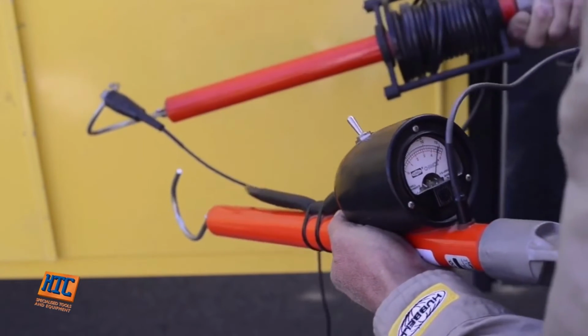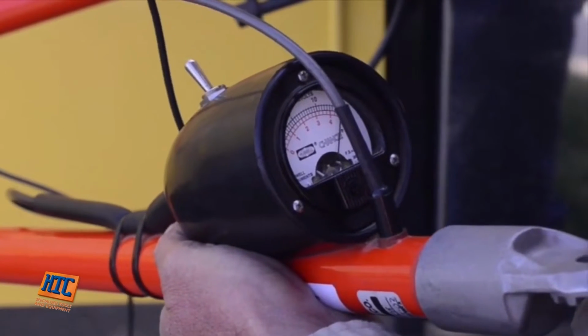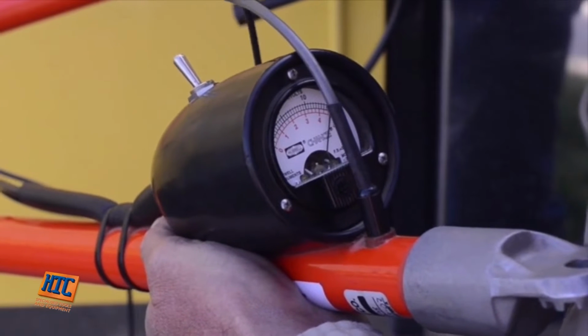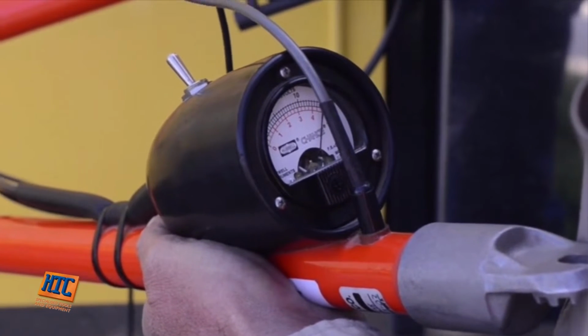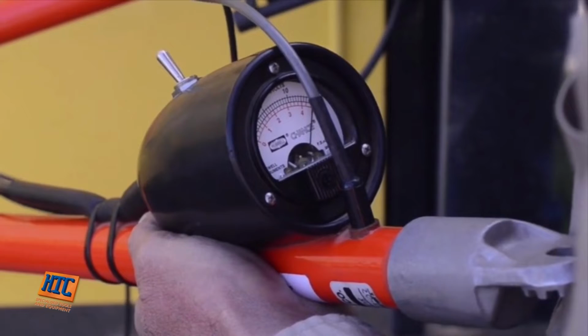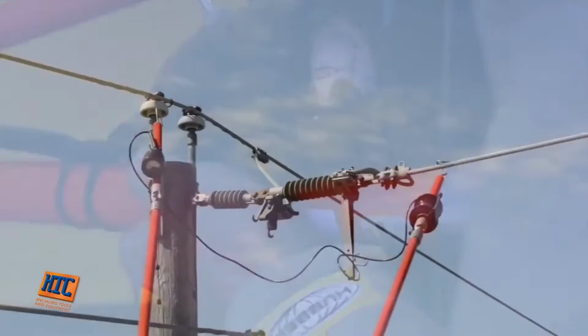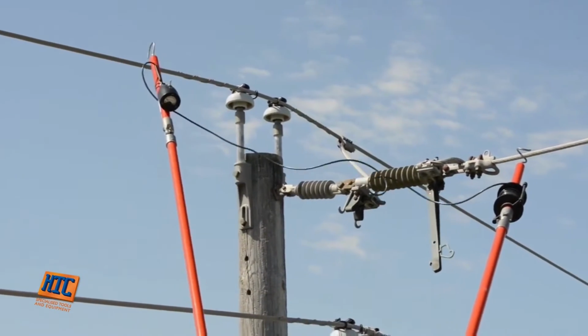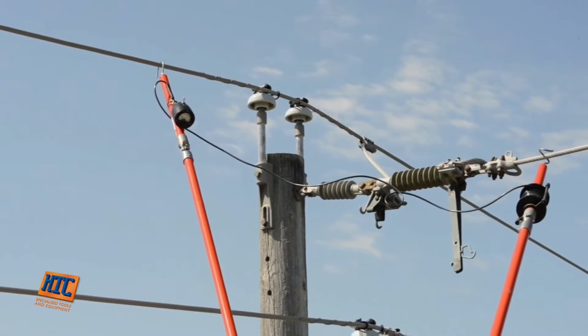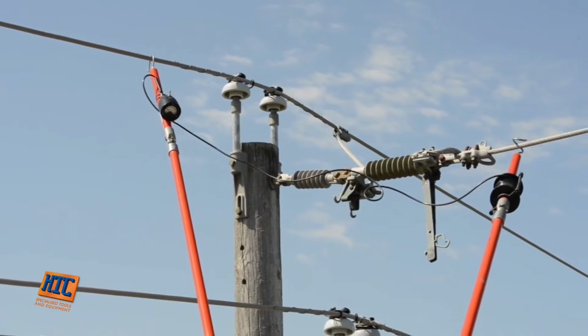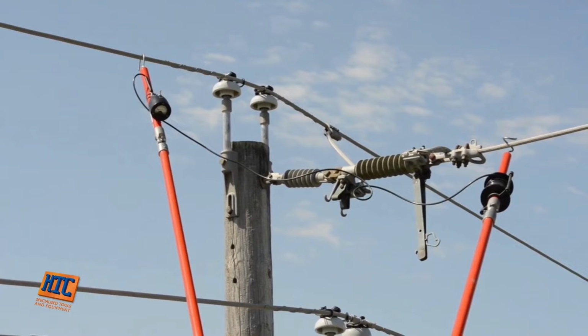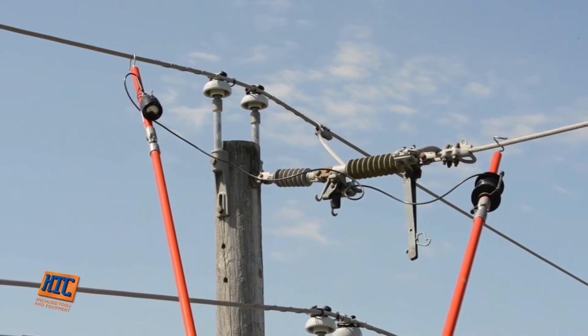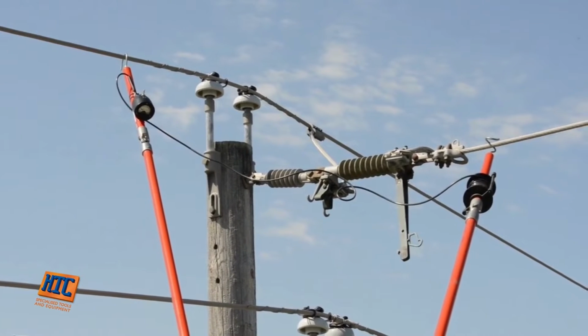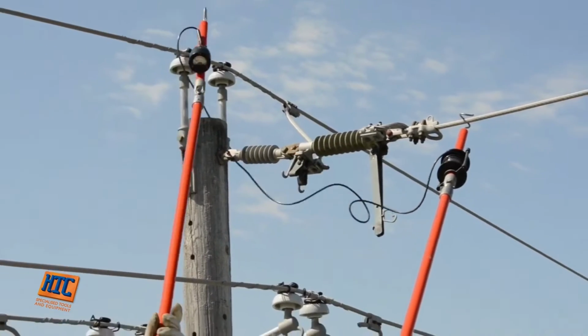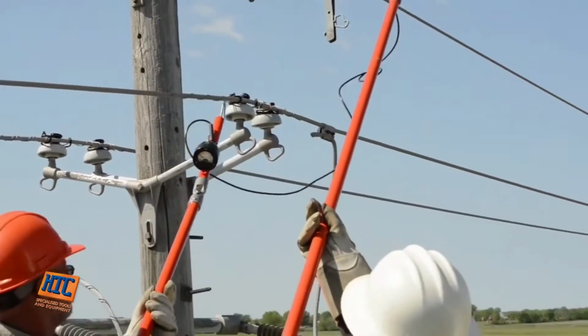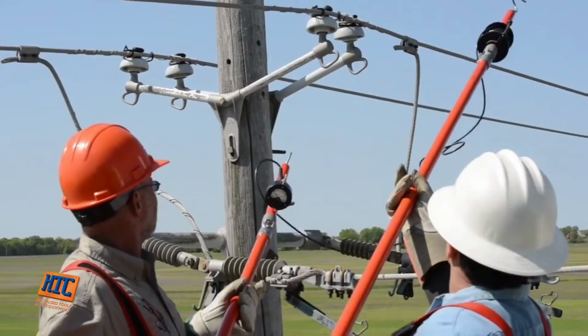Flip on the polarity switch. Notice that the needle deflected approximately 3/4 of the meter scale when checking both sticks. Install phasing tester on appropriate length universal sticks for the voltage to be worked. To determine phase relationships on system voltages up to 345 kV, each operator places a hook on the selected conductor. If the two conductors are in phase, the meter registers near zero. When the two conductors are out of phase, the meter indicates actual voltage potential.